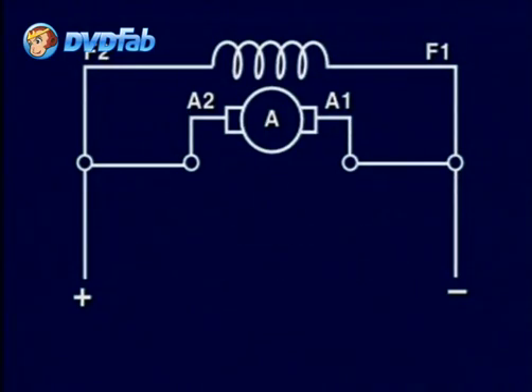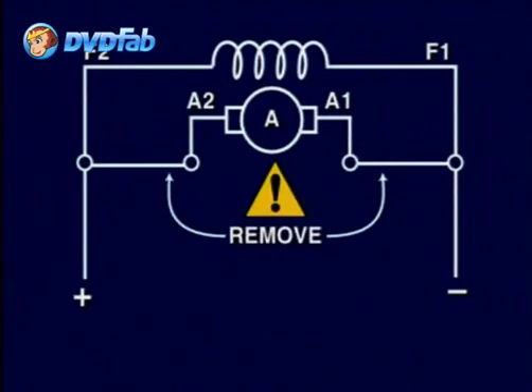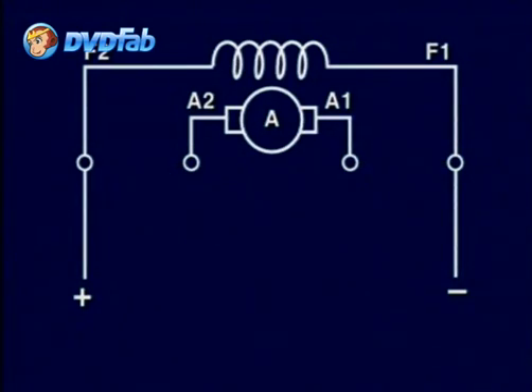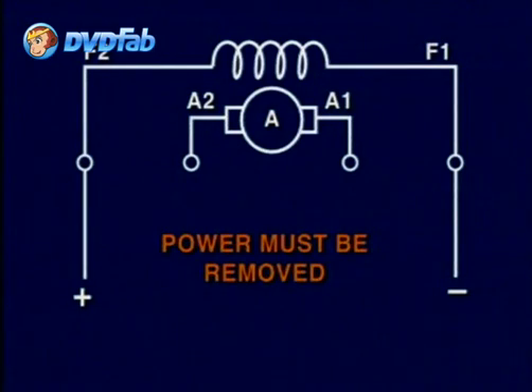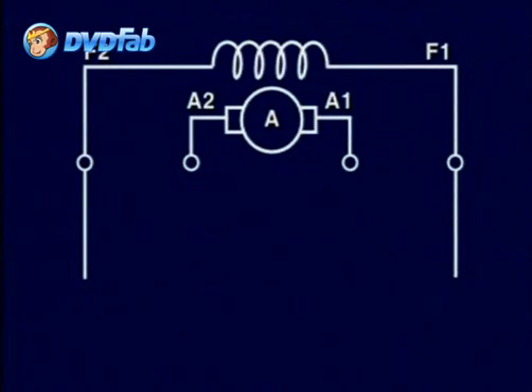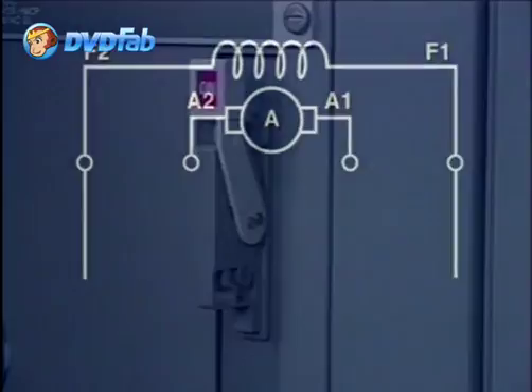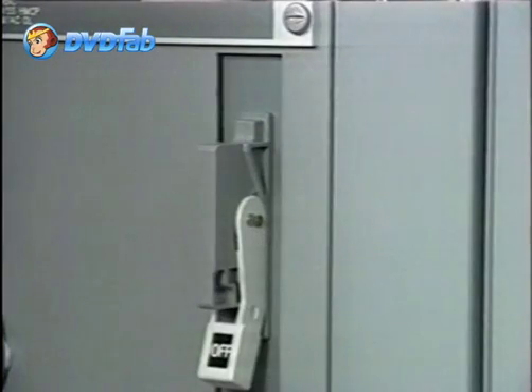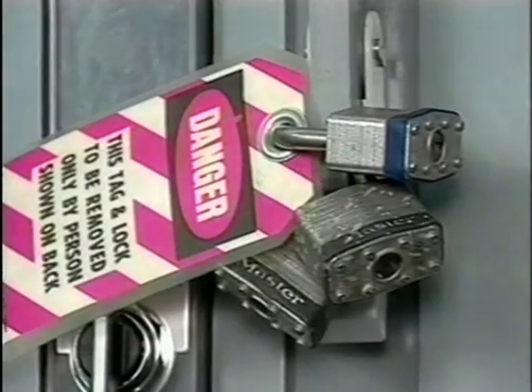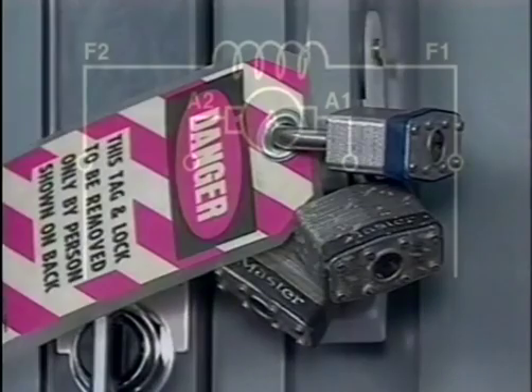To test the field winding, you must remove the shunt connection from the armature. Otherwise, you won't be able to detect an open in the field winding because the armature is connected in parallel and you could read continuity in the armature. Make sure that you remove the power to the motor circuit before starting to test the motor and that you perform the proper lockout after the disconnect has been opened so that nobody can turn on the power to the motor while you're working on it.